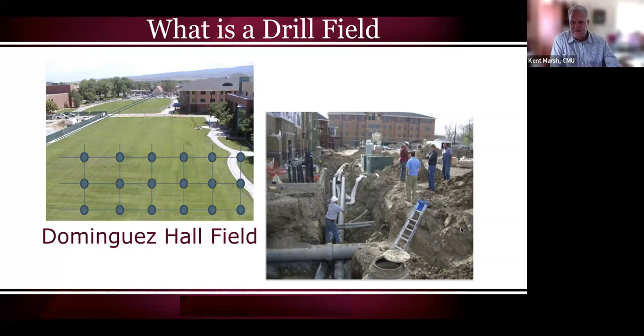And then we take one side of that loop and move it over 25 feet, where we go down 600 feet into the ground again, come back the other side of the hole up to within 5 feet of the surface of the ground, and then we go back down, and so on and so forth. Those pipes that are installed in a drill field are then connected to larger pipes that bring that water resource into a pumping station. Next slide, please.